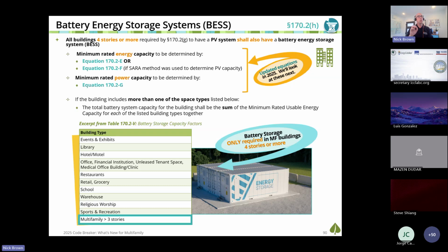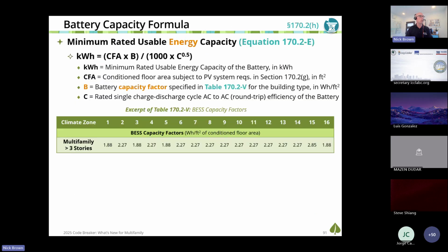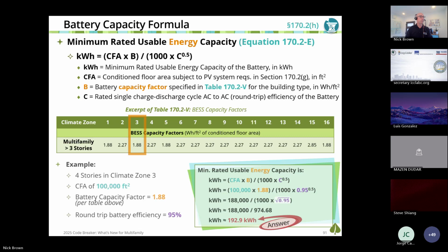And if you have a multi-use building, you're going to calculate the battery calculation by building type and sum them together, or the performance software will do this for you. So here's the equation. The size of the battery is the conditioned floor area times factor B in this chart, over 1,000 times the square root of the round trip efficiency of the battery.